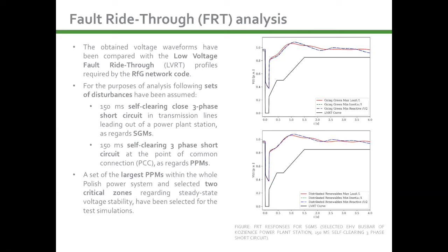The FRT response curves for both synchronous generation and non-synchronous generation units within the maximum load operational snapshot tend to have less oscillation than for the minimum inertia and minimum reactive ones, as you can observe in the presented figures. For power park modules, there has been no significant impact observed of different operational cases on fault ride through responses. The differences between fault ride through plots representing maximum load and other operational snapshots can be explained by greater power stiffness for the maximum load conditions, related to lower synchronous to non-synchronous penetration level values and higher synchronous generation level.